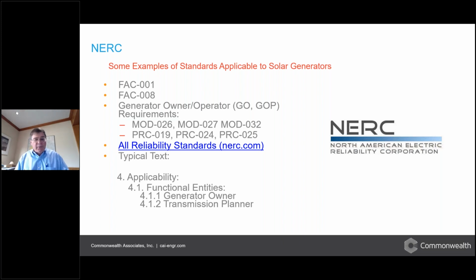And the industry was afraid that was going to cause a lot of regulation, so they formed the electric reliability council and said, hey, look, we're taking care of the problems. So NERC existed 30 years before open access, and they got themselves designated as the ERO. It's important to remember this when you're talking about all the FERC regulations and rules, is where the actual authority comes from. So on my list, I've listed FAC-001.